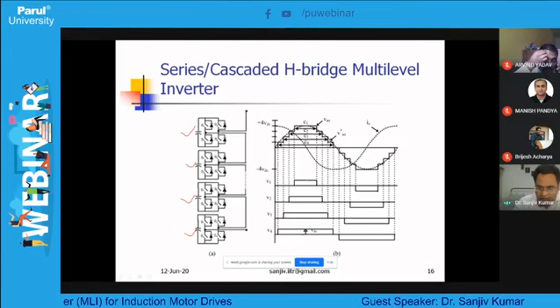And this is the 3 phase. You can notice we require 4 DC sources. Here it is shown as a capacitor, but in actual you require isolated DC sources. The purpose of showing the capacitor here is that a DC battery does not exist in the industry. You have to generate the DC voltage from AC, which means you use a rectifier, then across the output you put a capacitor so that this voltage is constant and you have the DC link. That is why in this figure a capacitor is shown. So you require 4 plus 4 plus 4, that means 12 DC sources, all isolated in nature, right?